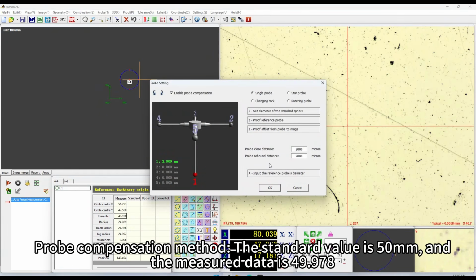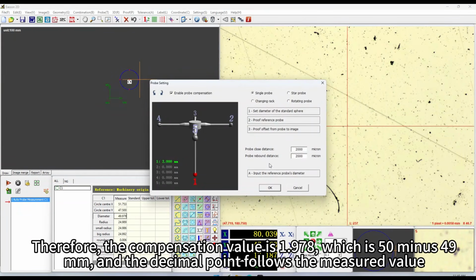Probe compensation method. The standard value is 50 mm, and the measured data is 49.978. Therefore, the compensation value is 1.978, which is 50 minus 49 mm, and the decimal point follows the measured value.